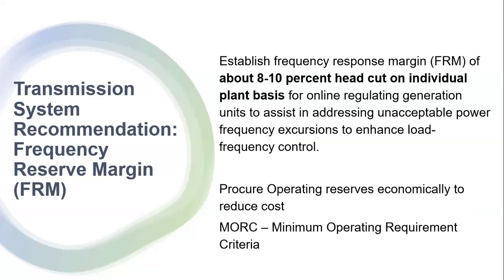For every generator, you have the Pmin and Pmax. The goal is that when you have frequency problems, you may get cascading effects into other control areas - like CEB, Ivory Coast, Benin, Togo, or Upper Volta - it goes around the whole system. So to address additional security for frequency, you leave about 6 to 8% of the generator Pmax unused. If the Pmax is 100, you leave 10 megawatts at the top at all times - unless, of course, you need everything. Here we have 5,740 installed and 4,000 megawatt load; even though you have about 5,700 megawatts of generation installed, you still have problems serving the load, and this all ties into the location issues we discussed.